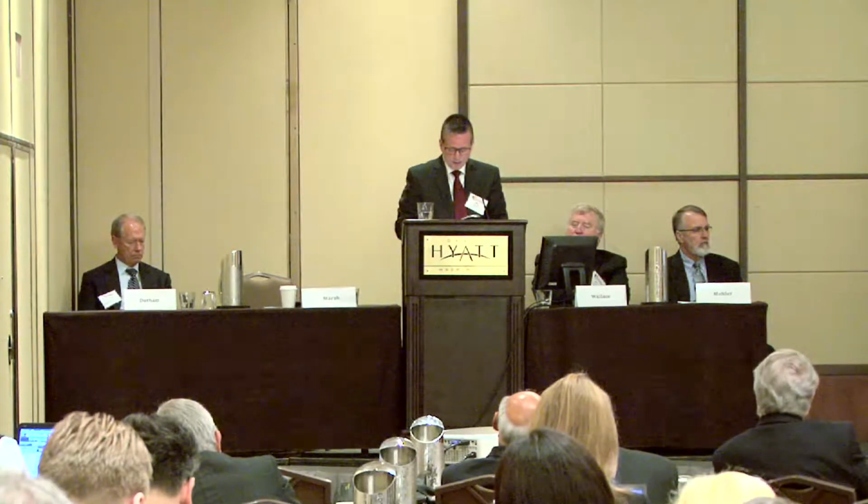And essentially, the regulation requires new and existing facilities to operate as clean as natural gas facilities. The regulation is 420 tons of CO2 per gigawatt hour. Boundary Dam's Unit 3 was 1,100 tons, but today, with 90% capture, with our carbon capture facility, we'll operate at full capacity and emit only 140 tons of CO2, essentially three times cleaner than a natural gas facility.